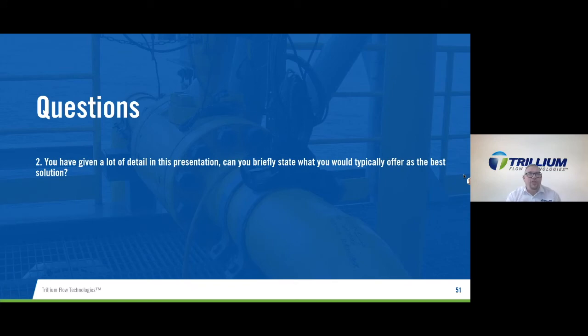So another typical question that we get asked: you've given a lot of detail in this presentation. Can you briefly state what would be your typical offering as a best solution? Well, obviously, there are many factors to take into account when selecting the best valve solution. Where there are concerns and known sand content, it's best to discuss with our sales application team. In general, it's largely dependent on the pressure drop and the amount of sand. We would most normally recommend our Tungsten Carbide multi-flow trim or our extreme trims. These provide the best flow path through the valve, reducing erosion and blockages.